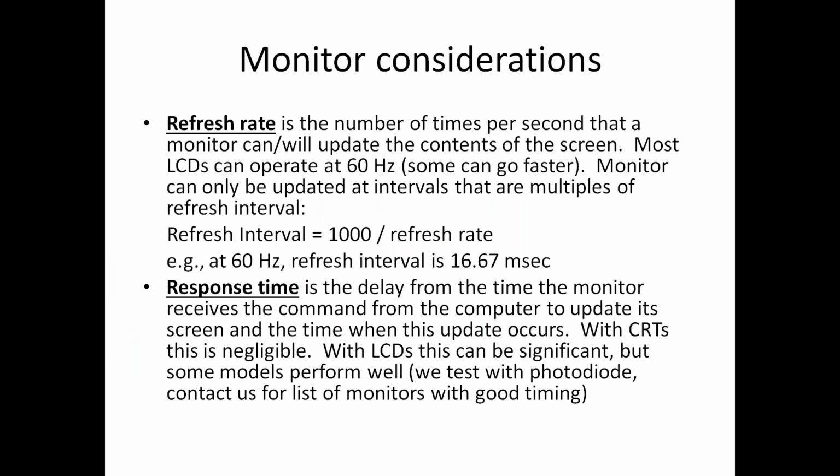The response time is the difference between the time when the monitor receives that command to update and the time when the screen actually changes, or that update is actually implemented. The way we test monitors to make sure they perform as advertised, because it's important for experiments that monitors perform well, is by putting a little photodiode up to the screen and switching the screen rapidly between black and white, for example.